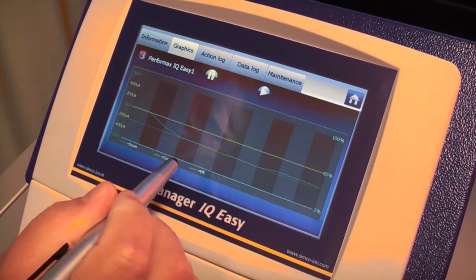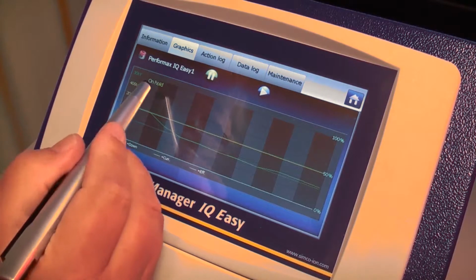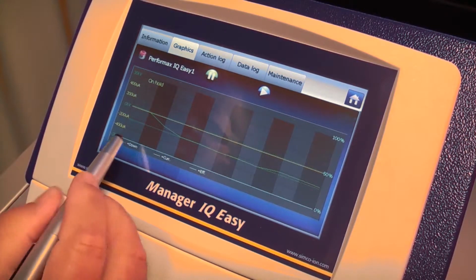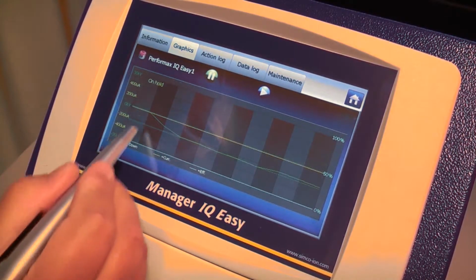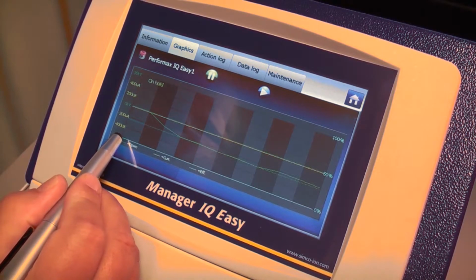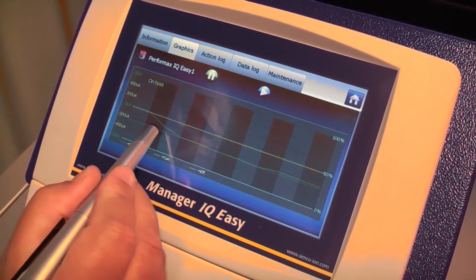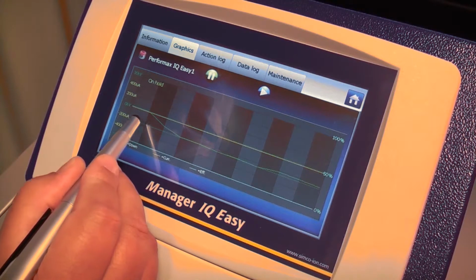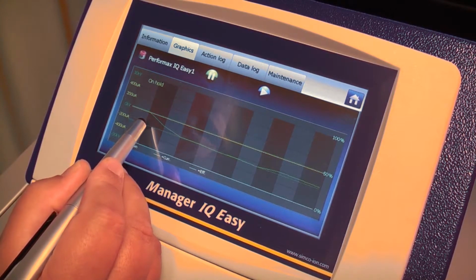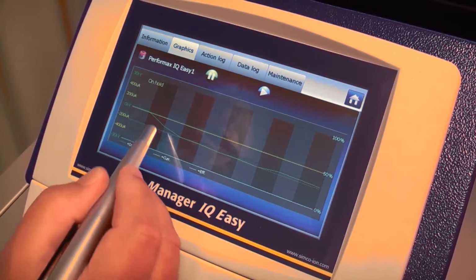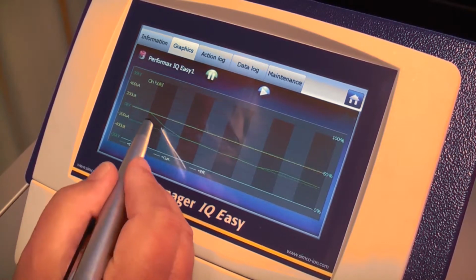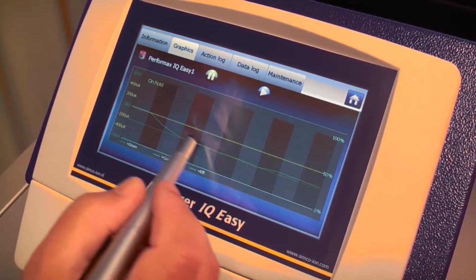You can press the graph and it will hold. We can see now the scale of the graph is minus 30 kilovolts, meaning half of the scale is 15 kilovolts, so this is close to 12 kilovolts, 11, 12 kilovolts. It is exactly the same as I have set in the charging generator.